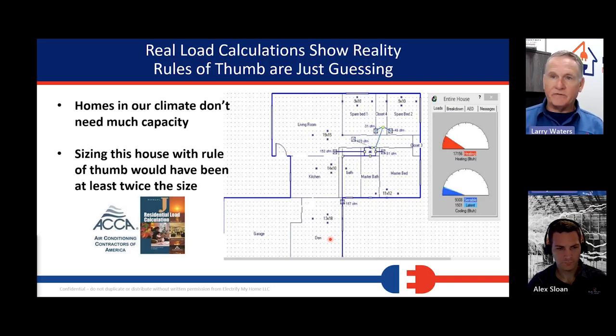This is a load calculation on a 1,500 square foot house in Fairfield, California. There was a 60,000 BTU furnace in this house and a 3-ton air conditioner, which is typical for a 1,500 square foot house. That's what they all got. This house was built in 1954. The system we pulled out was from the late 1990s, I think, like a 1997 system. So that means it had a system in there before that, and somebody came in and put this other system in, either using a rule of thumb, saying it's a 1,500 square foot house, 500 square feet per ton, we need a 3-ton system, and that's what they put in.